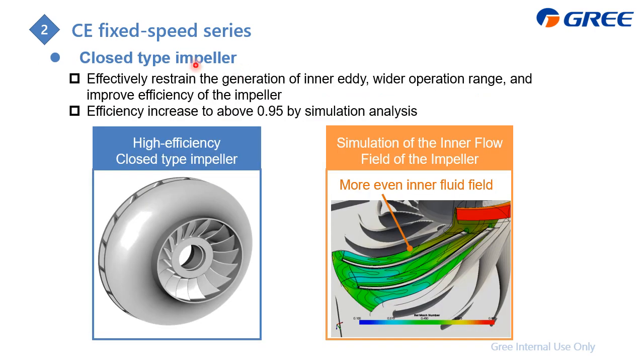And the next feature is the closed-type impeller. Just like this one, you can find it is closed-type. And the benefit is it can effectively restrain the generation of the inner eddy, widen the operation range, and improve the efficiency of the impeller. And we also made a simulation that this can efficiently increase the efficiency to above 0.95, which also means the inside flow is more even and smoother. This can lower the resistance.